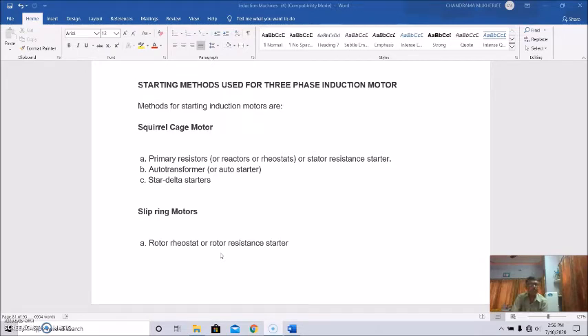So let us start with our discussions, that is, the starting methods used for the three-phase squirrel cage induction motor. Basically, there are three methods we are using. One is primary resistors, or you can say reactors or rheostats, or a resistance starter. Secondly, we use an auto transformer or auto starter, and thirdly, the most important one, the star delta starter. And for slip ring motors, we generally use a rotor rheostat or rotor resistance starter.